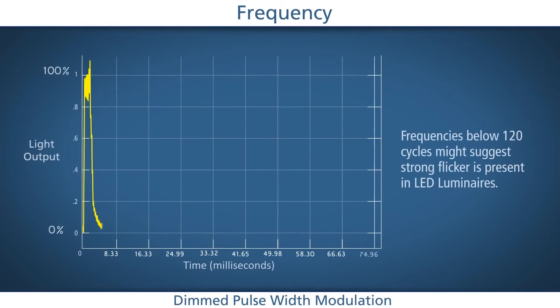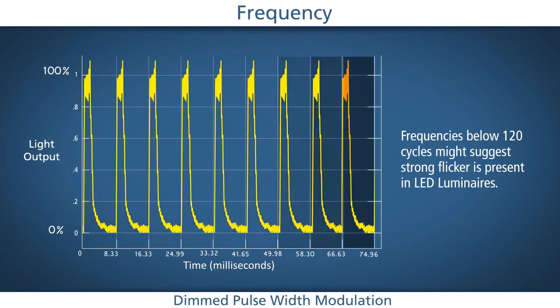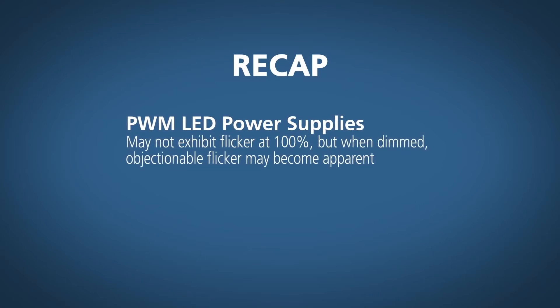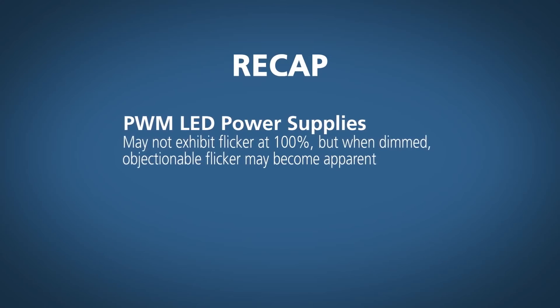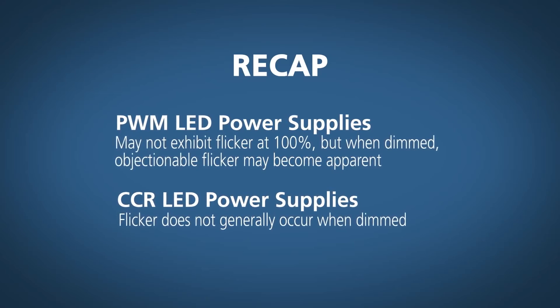Record the frequency of current pulses reaching the LEDs. Research has shown that pulses in the range of 120 cycles per second may be perceived as significant flicker. To summarize: PWM LED power supplies may not exhibit flicker at 100% light output, but when dimmed, objectionable flicker may become apparent. This is generally not the case with CCR LED power supplies.